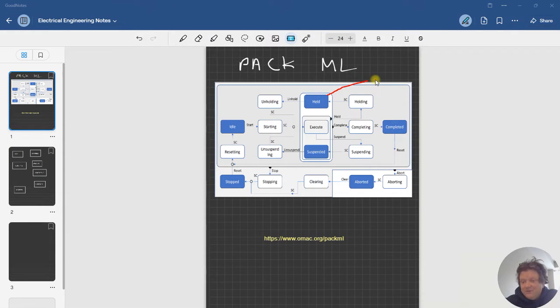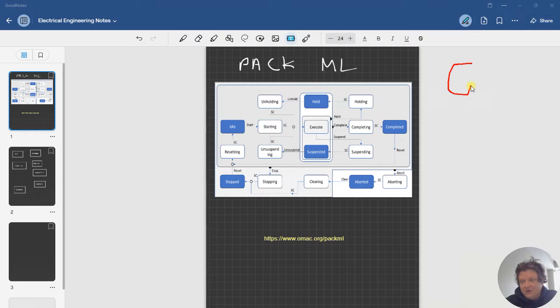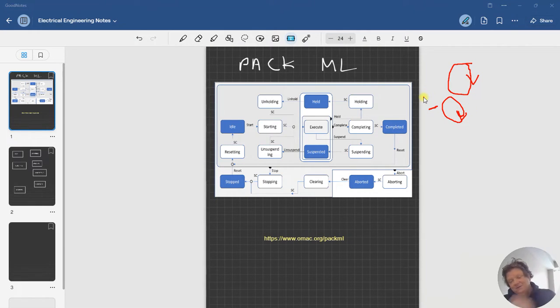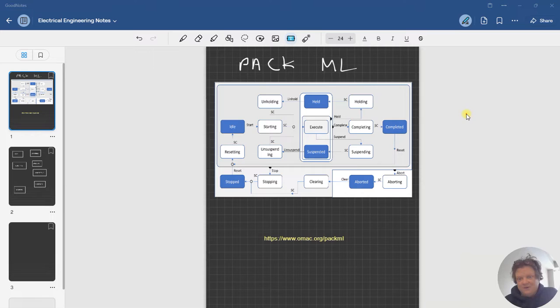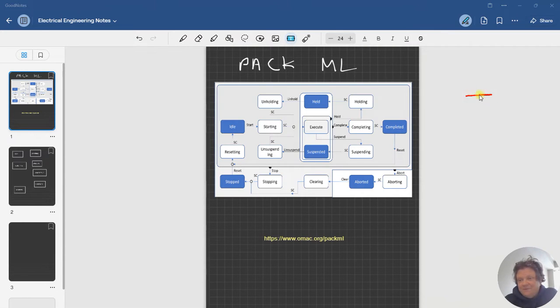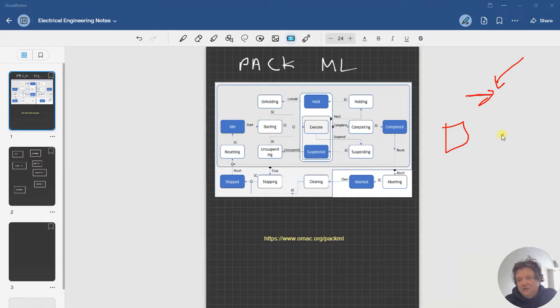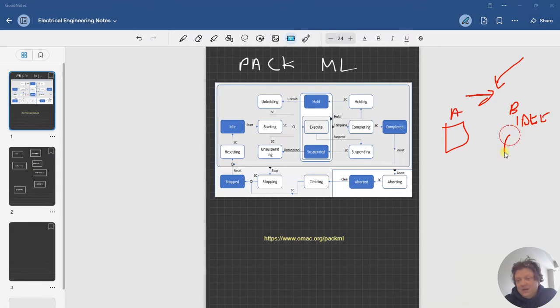is my conveyor empty? Yeah, my conveyor is empty, so just hang on a minute. In that case, you come out, you have your regular one-time program. Say we're cycling through in the PLC with the main or whatever your main routine is, whether you call it main or whether it's just a hundred millisecond cycle. Say you get to step five and you're looking for product coming in on the assembly line and it's not there.